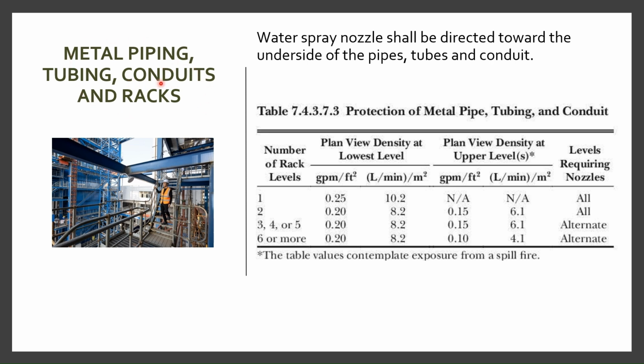If you look at the screen, the design densities are also provided here. I will explain to you in a while. Water spray nozzles shall be directed toward the underside of the pipes, tubes and conduits. So nozzles shall be positioned less than or equal to 2.5 feet below the bottom of the rack. That one we will discuss when we explore more into the design part of these particular items. So for now just look at this particular table.